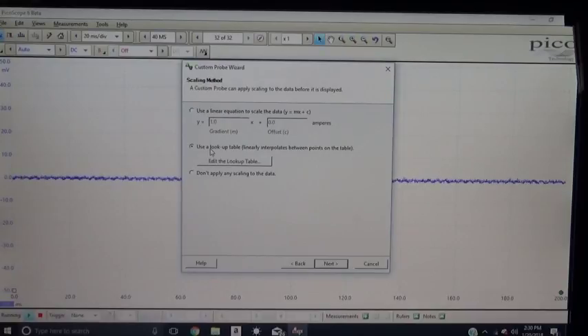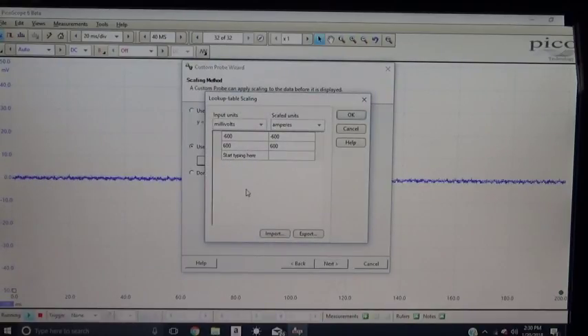And this time we're going to use a lookup table. Here, what I did is set 1 millivolt equal to 1 amp, so you're going to change, make sure you change to millivolts here, okay, so you're going to set it up to millivolts. So minus 600 is minus 600 amps, and 600 millivolts is equal to 600 amps. That's all you need to do. The reason I got this negative number is because sometimes you're going to invert your amp clamp, and if you don't do this, you will not have any reading on your screen, it'll be zero, it won't read any negative numbers. So this is what you need to do to customize this one.